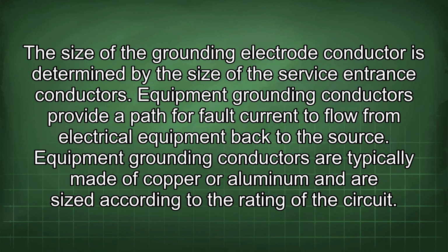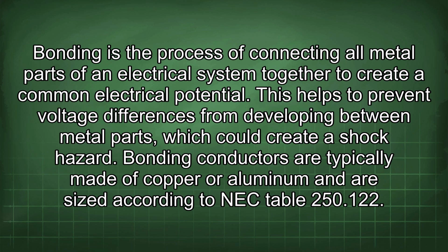Equipment grounding conductors provide a path for fault current to flow from electrical equipment back to the source. Equipment grounding conductors are typically made of copper or aluminum and are sized according to the rating of the circuit. Bonding is the process of connecting all metal parts of an electrical system together to create a common electrical potential. This helps to prevent voltage differences from developing between metal parts, which could create a shock hazard.